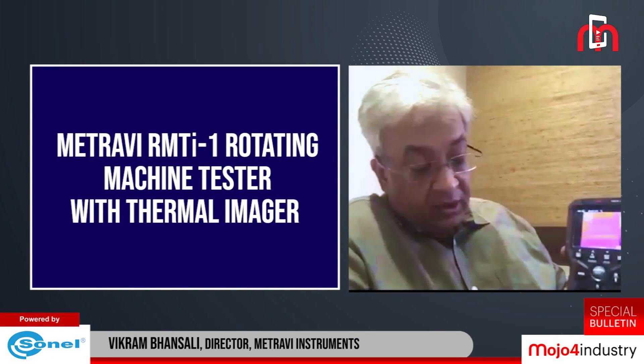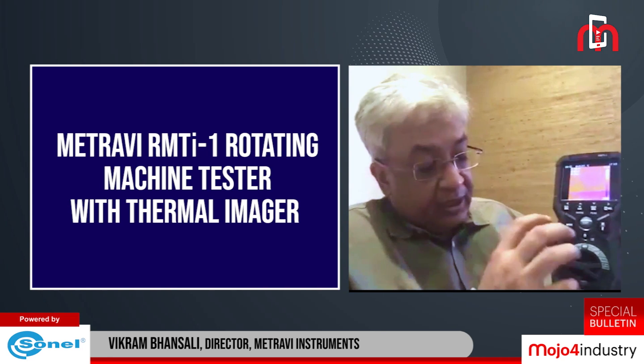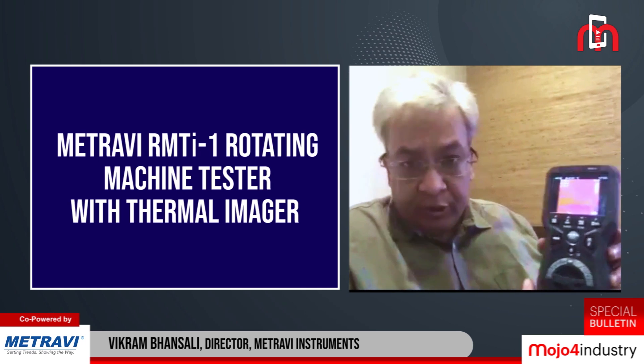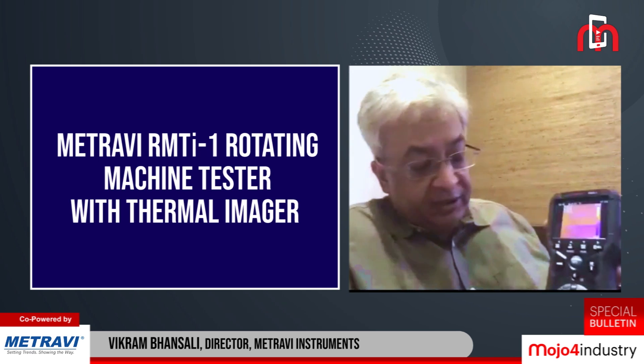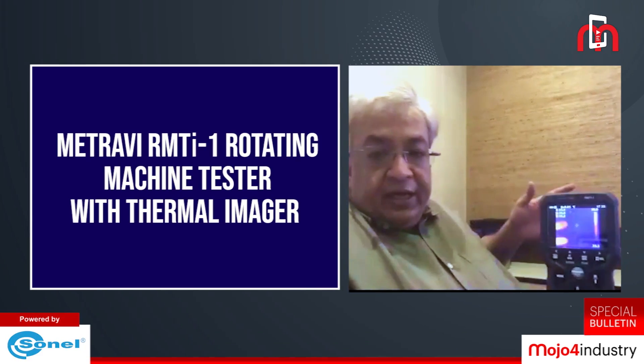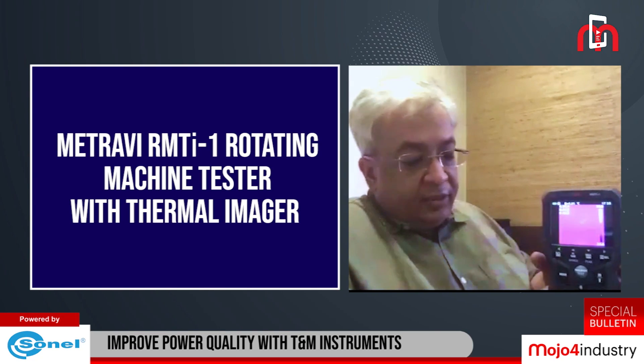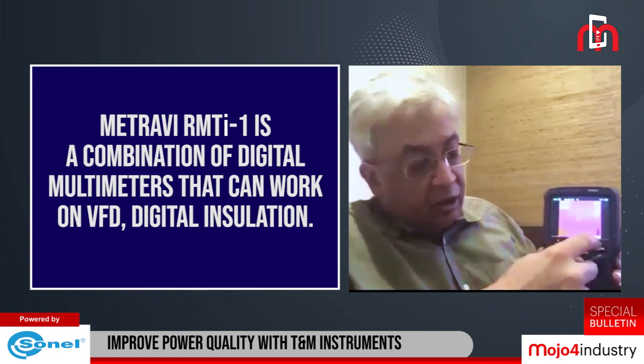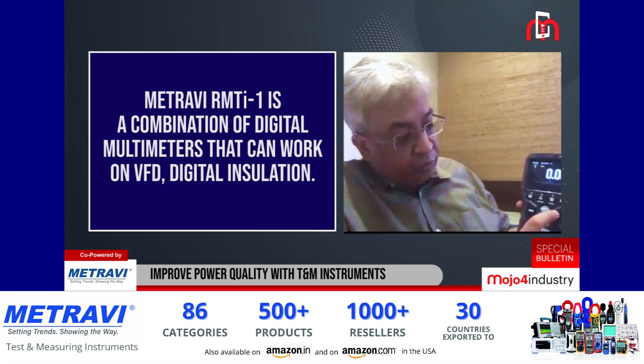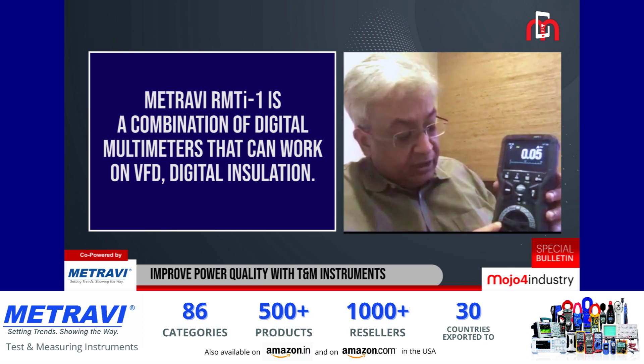This is an insulation tester with a milliohm meter that tests all possible parameters of rotating machines — any motor or generator. The unique feature of this instrument is it has a built-in thermal imager. If I put my hand behind it, you can see the fingers flickering. The color indicates temperature, and a color bar shows what each color represents. Additionally, you can record current up to a maximum of about 3000 amperes.